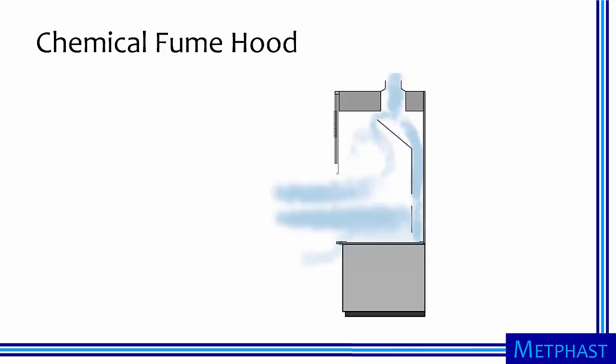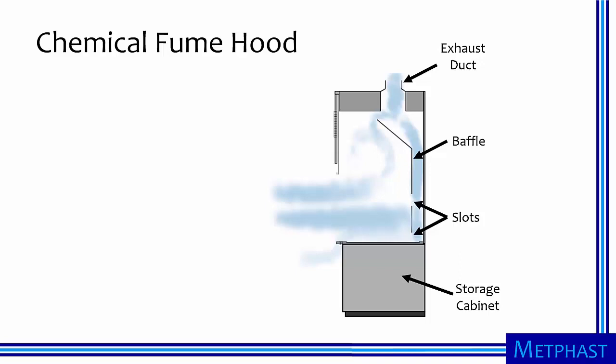Chemical fume hoods are an important class of enclosing hood. Shown here in side view, air is pulled from an exhaust duct with baffles and slots used to direct airflow. Often, a storage cabinet below the work surface is held at negative pressure for safe storage of chemicals. A sash is used to open and close the hood face, and its position changes the airflow patterns.